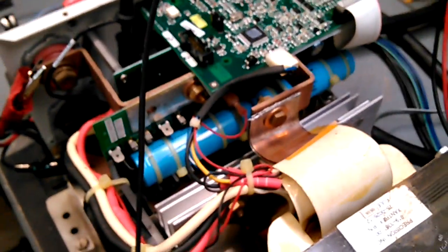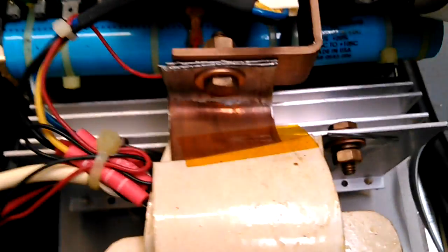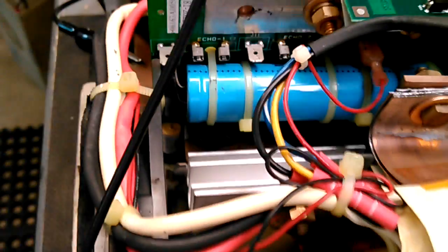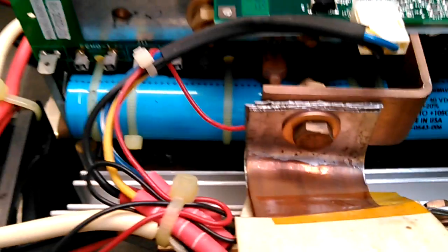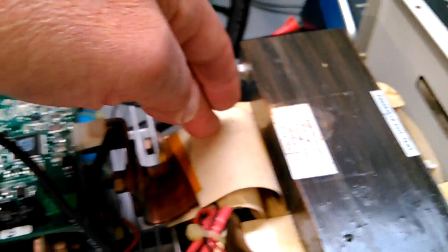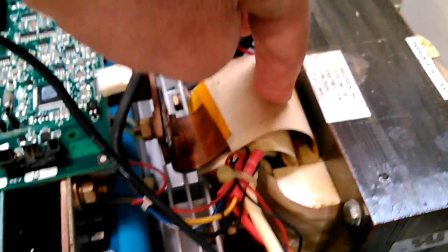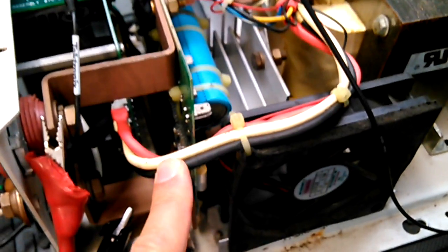Let's take a tour of the inside and you'll see how it all comes together. This section in the back is your heat sinks, with all your transistors tied into that for the invert function. Then of course filter capacitors, large transformer. The transformer steps the 12 volts that's being switched back and forth into the primary of the transformer. Those are the big heavy plate-like wires that go into the input side of the transformer, and then the output side is your standard output-looking wires from the transformer, your output AC, which then go into an AC board, relays and current sensors hidden down in here, and then out to your output.